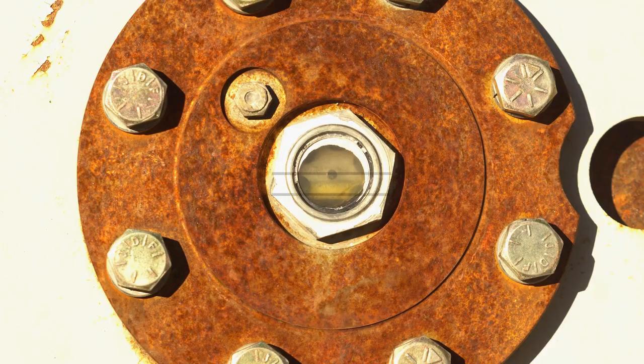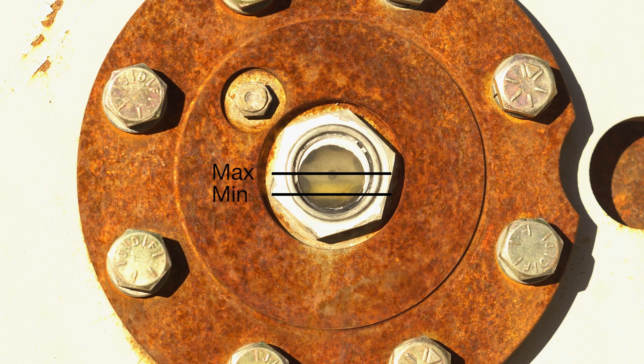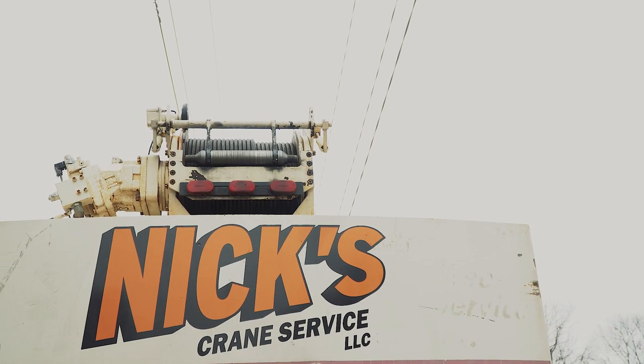Oil level must be maintained between the minimum and maximum levels — midway up the sight glass, or at the bottom of the level plug port, depending on the hoist model.